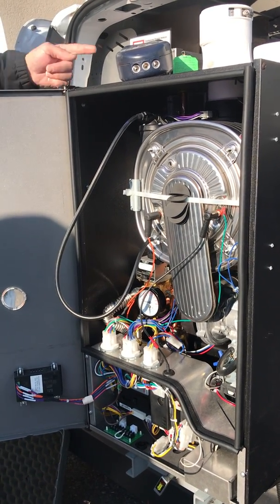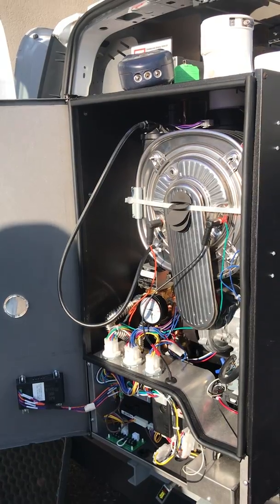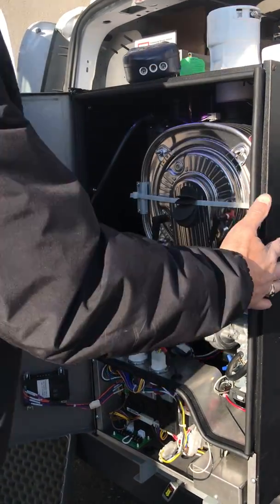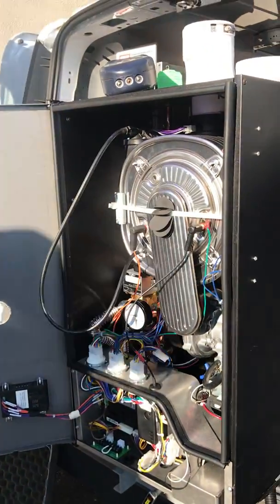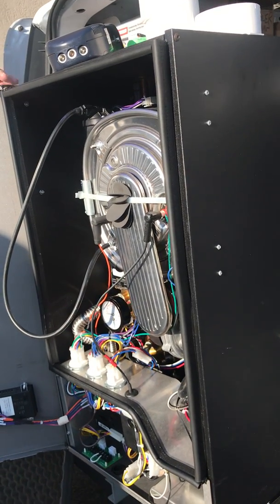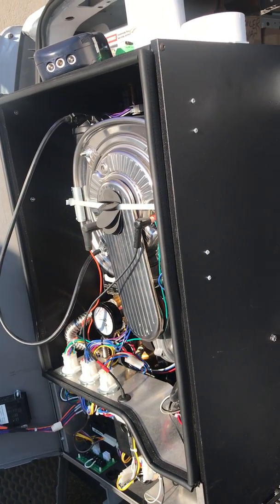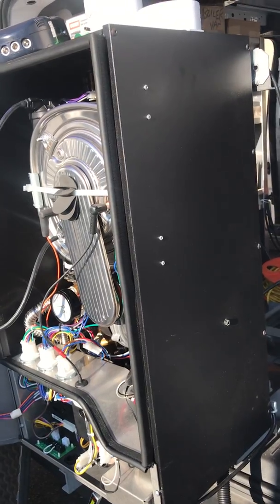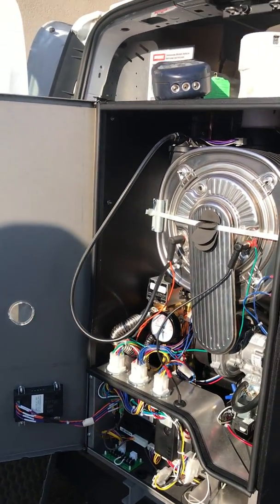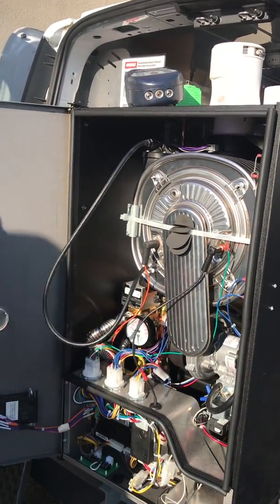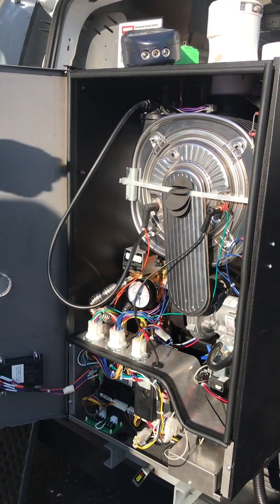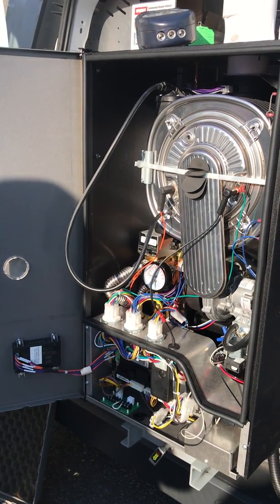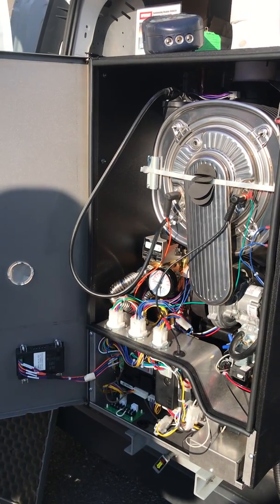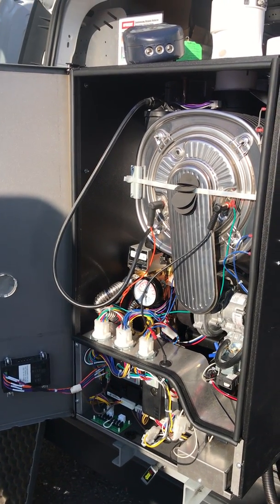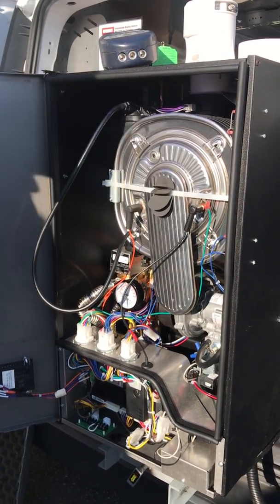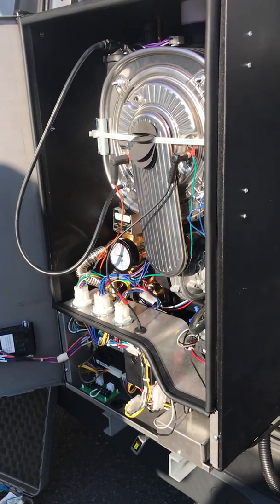These side panels can come off. So when you install this, if you put it in real tight, and you really wanted to get into this thing, this panel can come off the side, and that basically allows us to totally get in where this circulator is. This comes out of the way and I can come in this way, but you can take off both sides if you want. We do not require clearance. I'm just letting you know if you want to take it off. I would probably leave some space on this side. I don't normally take this side off, but if I want to, I can.